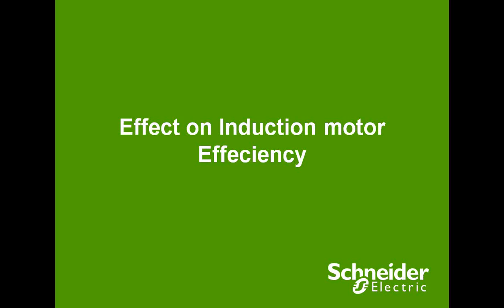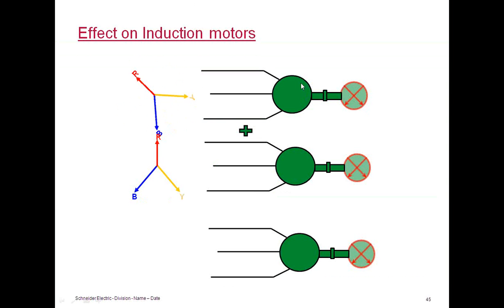So we come to the induction motor. How exactly will harmonics influence the efficiency of an induction motor? Let's assume this is an induction motor. It has a 3-phase input, and there is a mechanical shaft here coupling the load on the right-hand side. We'll assume we have an input supply, maybe 400 volts, 3-phase, 50 hertz. If you apply this input voltage, you will get some speed and torque on the rotor that will turn the load. Fifth harmonic, you remember, is minus sequence, that means it's clockwise rotation.